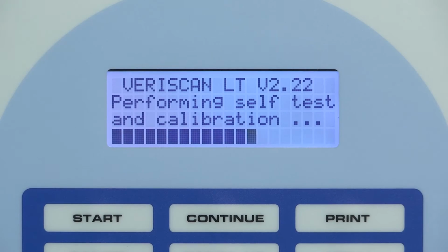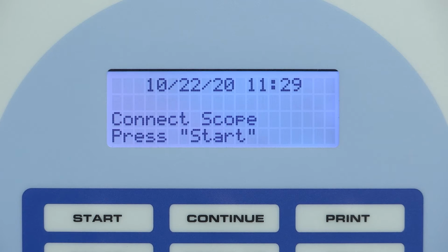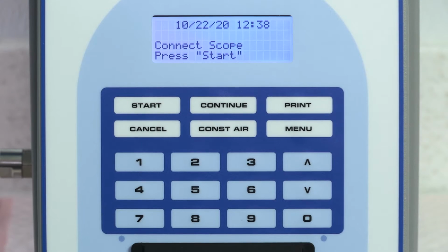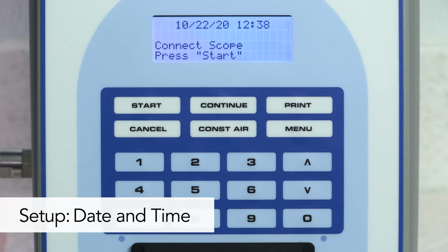Once it is turned on, the VERISCAN Leak Tester automatically performs an initialization process that includes a series of diagnostic program self-tests. When this process is successfully completed, the display shows the date and time. Connect scope and press Start. This indicates it is ready for the Daily Quality Assurance or QA test covered in the Daily Startup segment of this video. Let's walk through the process of setting the date and time on the VERISCAN Leak Tester.